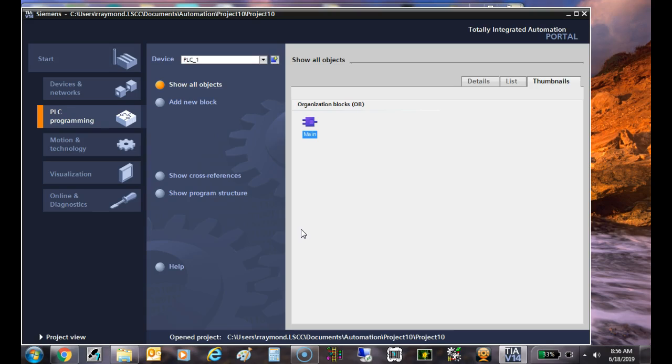So these clock files and these first scan bits are already built into the system. I'll show you how to access those through the status register. That's that S2 file over on the left-hand side, where you can access the first scan and that kind of stuff. On newer PLCs, they basically don't assign the memory. So what that means is, if you don't need that first scan, if you don't need those clocks, they require you to set them up. Does that make sense?